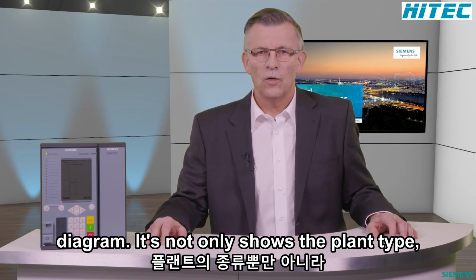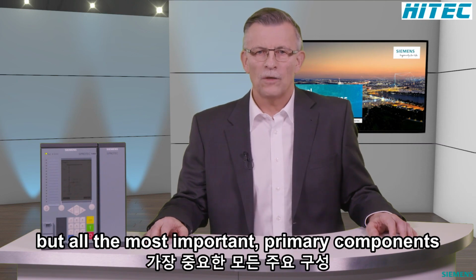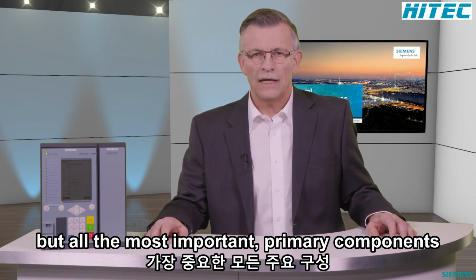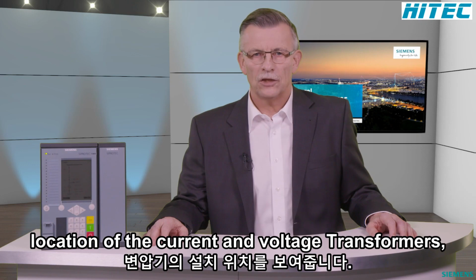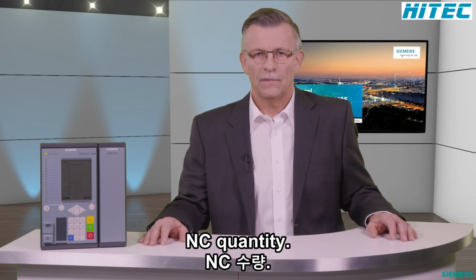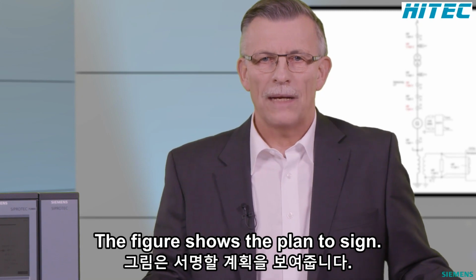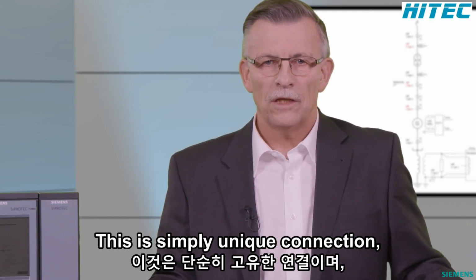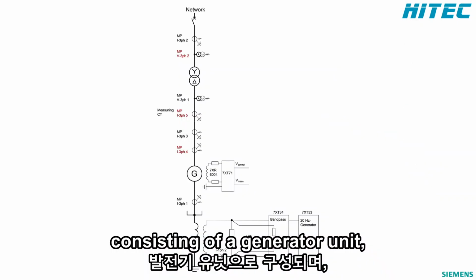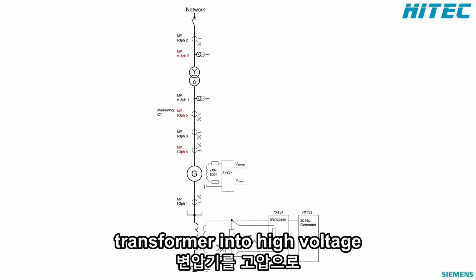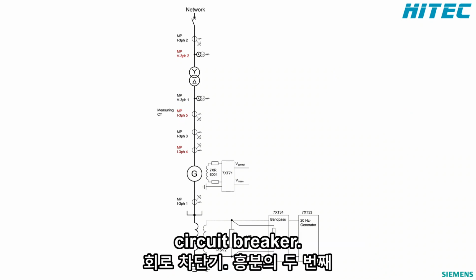It not only shows the plant type, but also the most important primary components and the installation location of the current and voltage transformers and their quantity. The figure shows the plant design. It's a simple unit connection consisting of a generator, unit transformer and a high voltage circuit breaker.